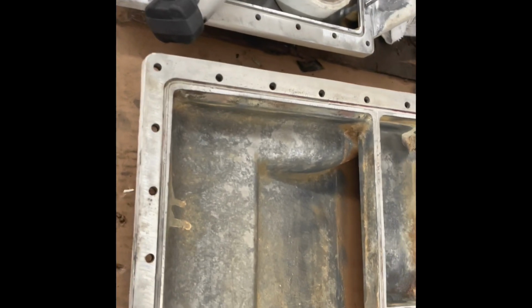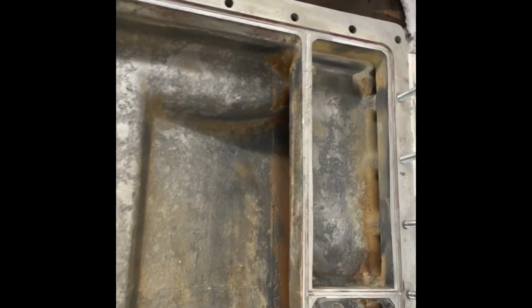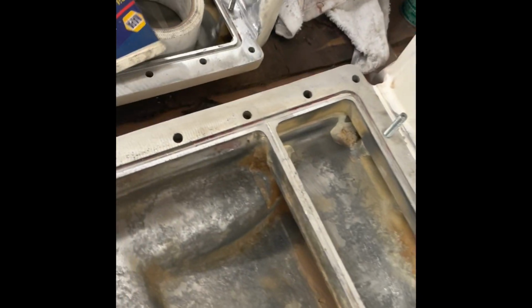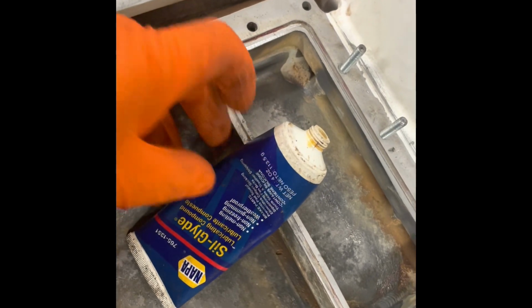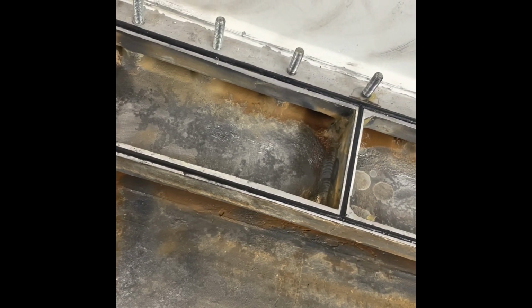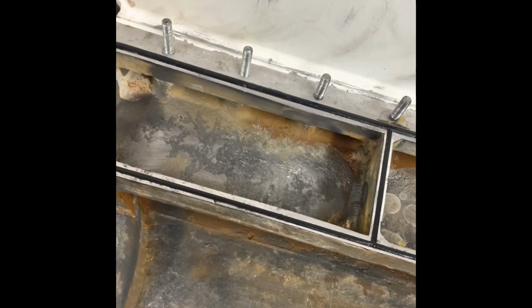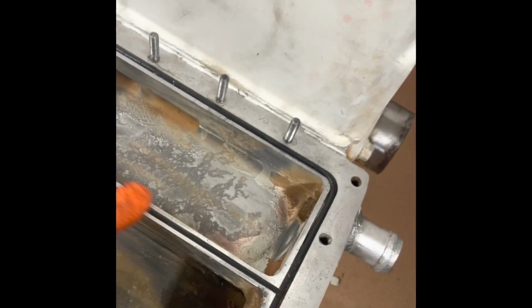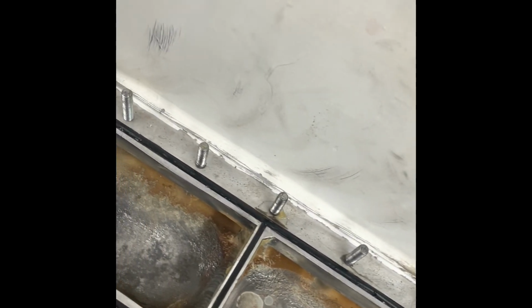All right, so here we are. We got our tanks relatively clean, wire wheeled, brushed out, clean gasket surface, cleaned out seal groove, studs removed, studs put back in, pressure washed the tanks. Now we put the gaskets in, and before I put this gasket in, I like to use a little Sil Glide, put a little grease inside the groove, holds the gasket in place, the seal. Just here and there, a little shot of grease down inside that groove. And I just go around and I coat the outside of the seal with some grease, Sil Glide.